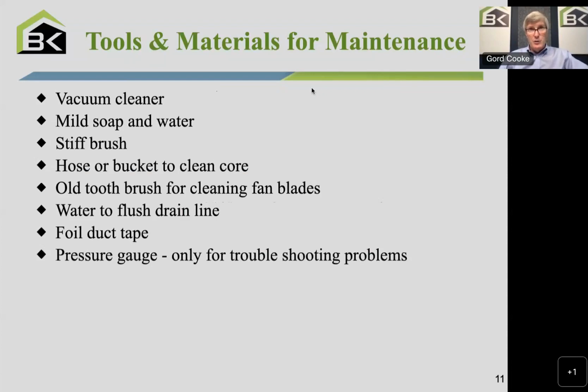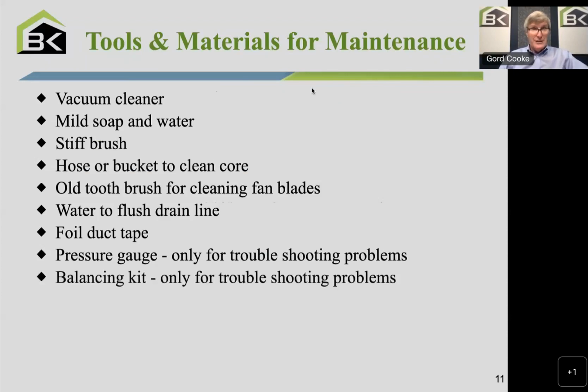And then if you were doing bigger maintenance, like balancing or troubleshooting problems with flows, you would need a pressure gauge. I'm not going to spend too much time on that today, just so that you know there are tools if you needed to diagnose problems with airflow in a house. Similarly, a balancing kit, typically not needed on an annual basis, only if there's problems with a unit. So those are the kinds of tools you need. And of course, maybe some common hand tools.